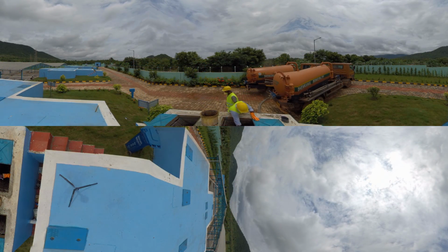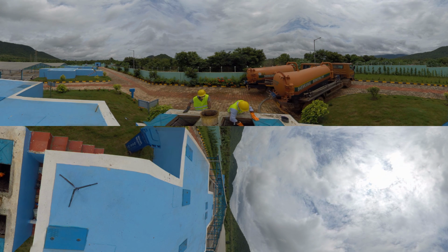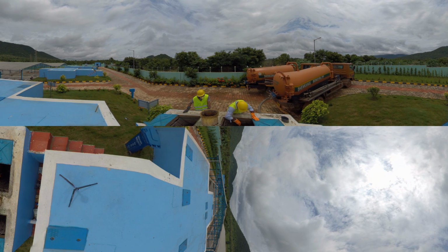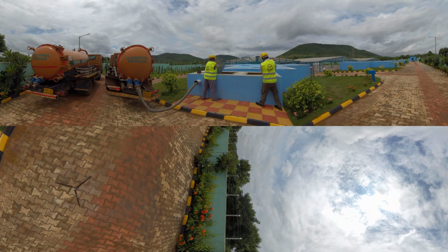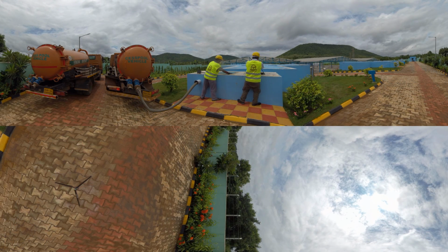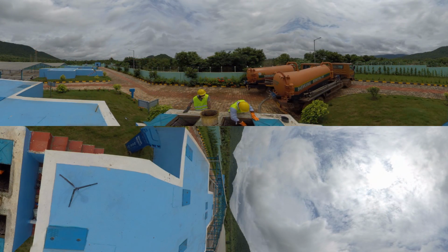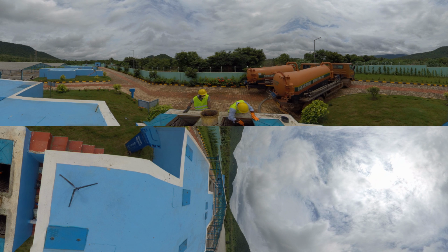To clean, open the inspection covers and using a trowel collect all the solid material accumulated on the screen into a bucket. Then, clean the bars of the screen using water. Remember to close the inspection covers once you are done. While cleaning the screen, you have to ensure that no solid particles enter the chamber.